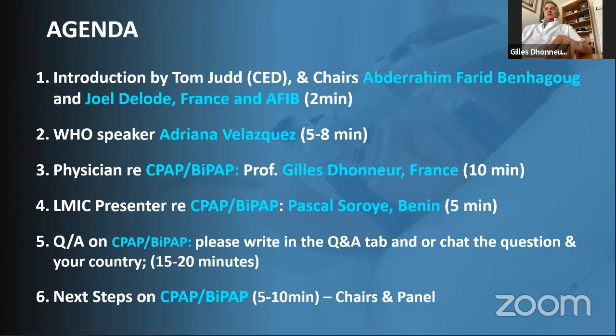There could be overpressure sometimes when you close the system and you blow inside the system. You will see in my slide, I gave you some bench tests of the CPAP of Boussignac. The Boussignac system is surprising: high inspiratory flow and never overpressure, unless you blow in it and you close the system. There are other pocket CPAP devices that allow you to perfectly set the maximum pressure in the airway, so these are safe. But with the CPAP of Boussignac, there's no fine tuning or anything.